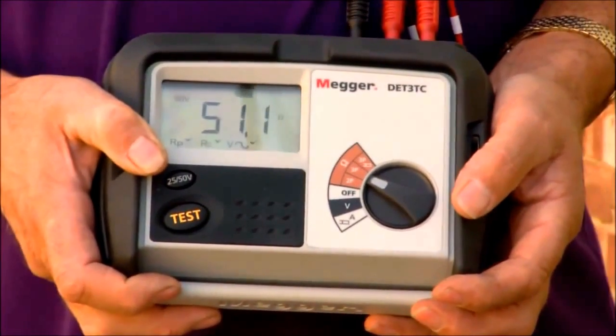I've already carried out that process. Just want to take a resistance value to see what difference it makes. We can see now that we've got a resistance value of 51.5. It's dramatically reduced the resistance value, so 2 earth electrodes would be better than 1 in this instance. And to get a very accurate reading, of course, what I would need to do now is repeat the 3 tests by moving the potential electrode 10% this way, 10% the other way, and taking an average of the 3 readings. And that would give me the reading I would write down on my test certificate.